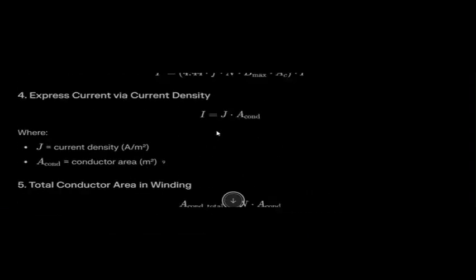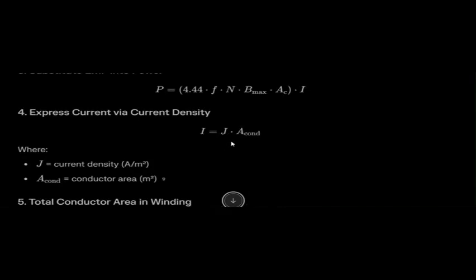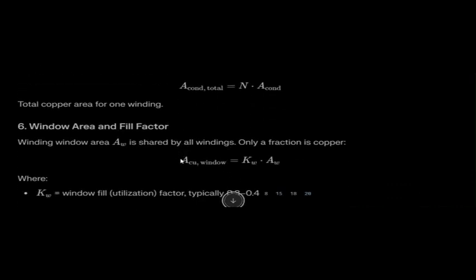And now we will notice that everything else is supposed to be the same for the primary winding and for the secondary, or secondaries. Really, the power is supposed to be the same, power in, power out. We are ignoring the losses now, but they are typically small enough, so the power can be assumed to be equal for simplicity. Frequency is the same, and Bmax is the same, and the core area is the same, and the J, the current density, is typically taken to be the same. In the optimal transformer, it is the same for the primary and the secondary, or a set of secondaries. So we have power balance, we have current density balance, and it will mean that the area of the conductors in the windings on the primary side and secondary side must be approximately equal as well. So we get the conductor area balance as well. So this N times conductor area is like 1/2 of the window area.